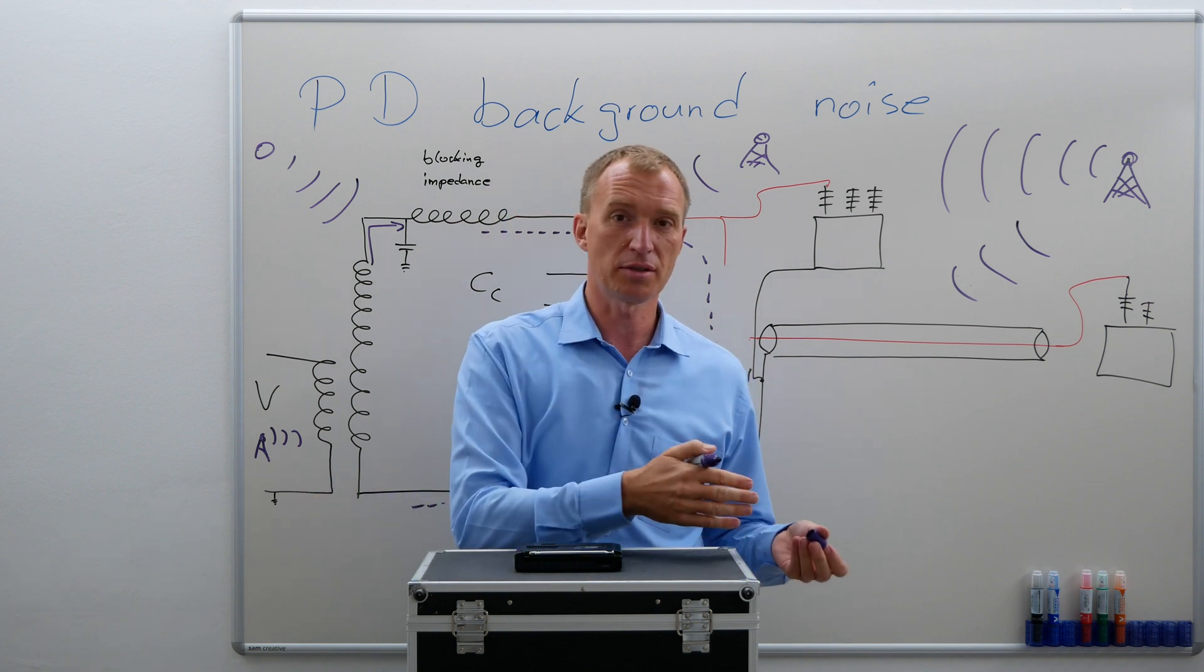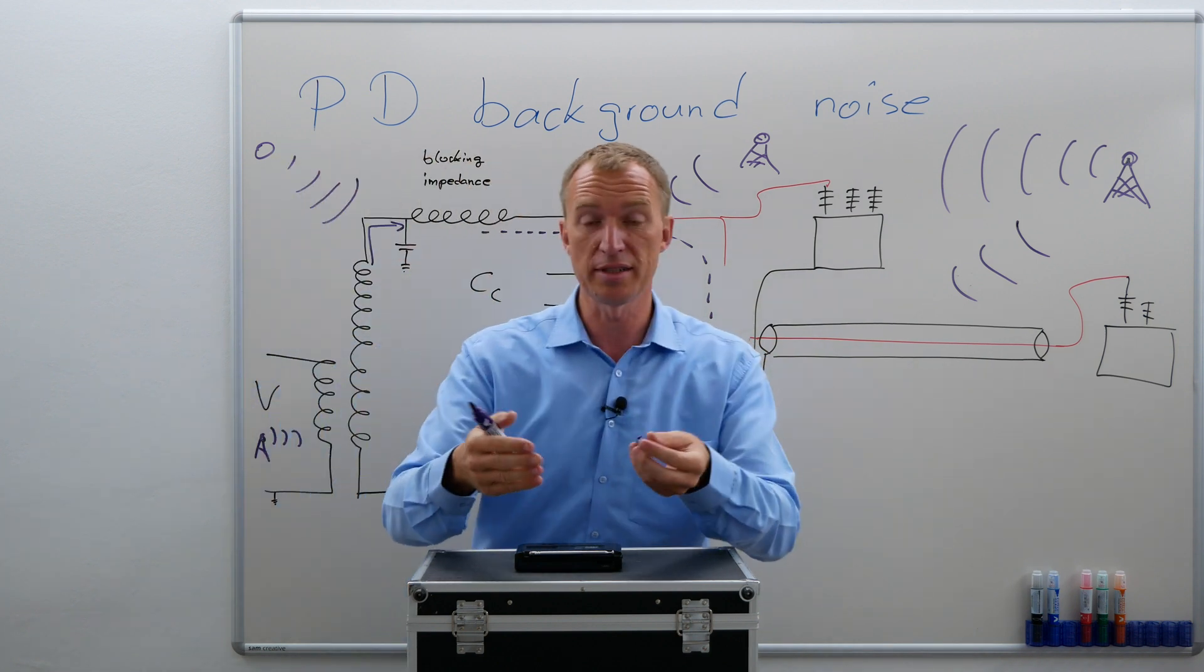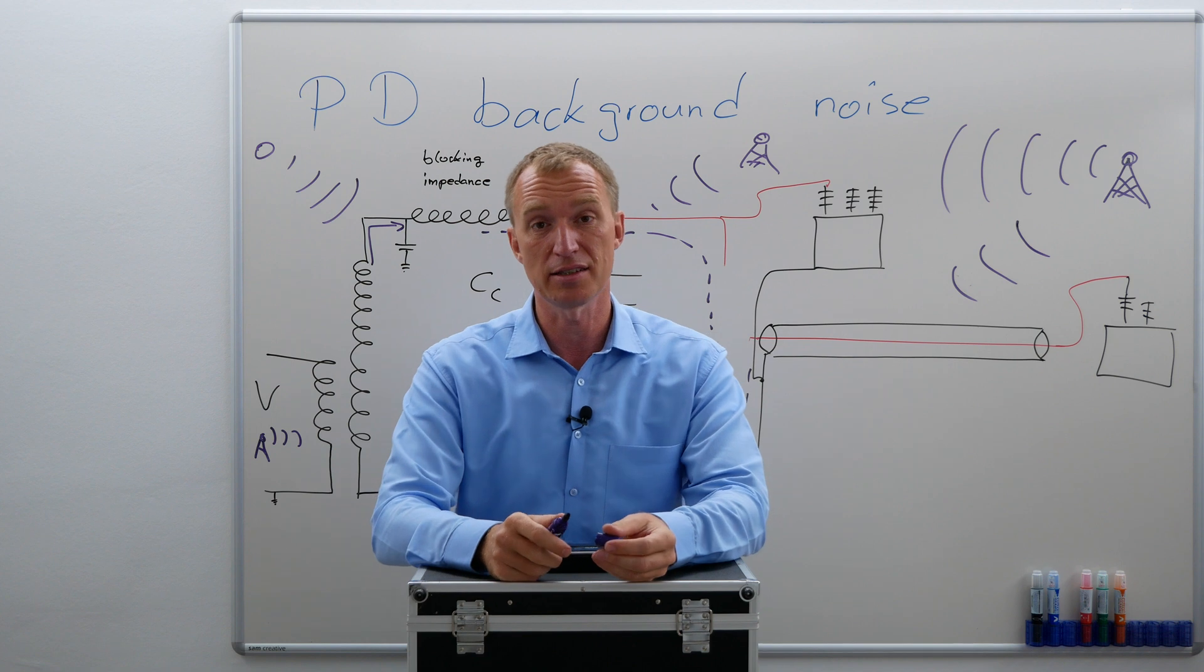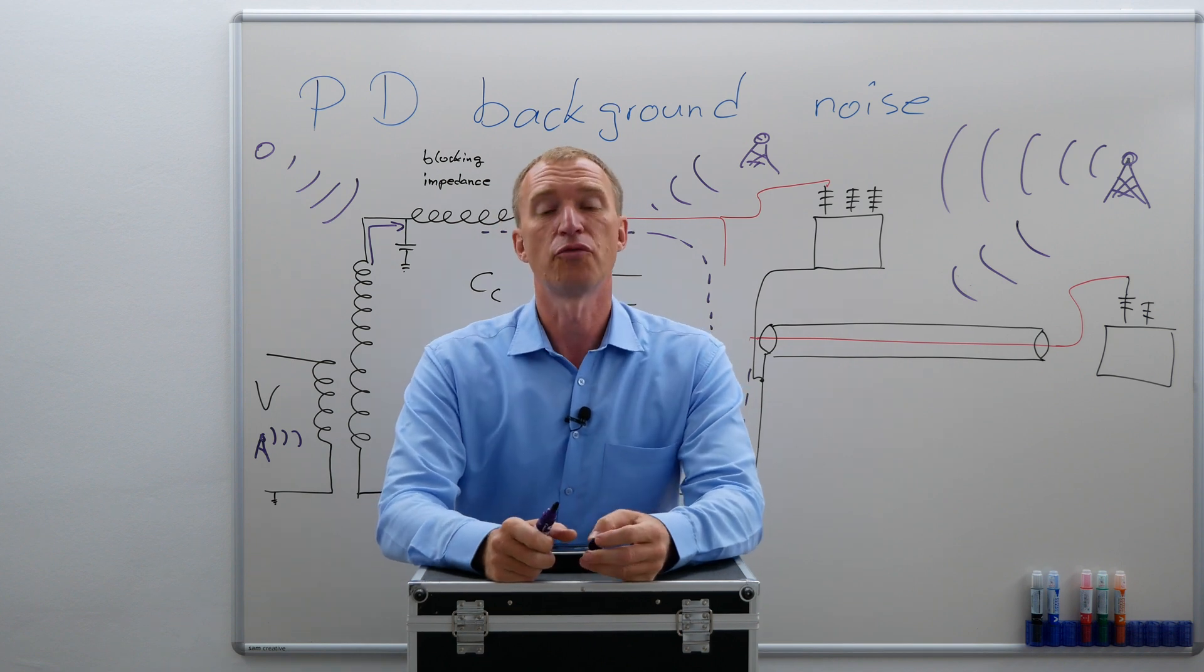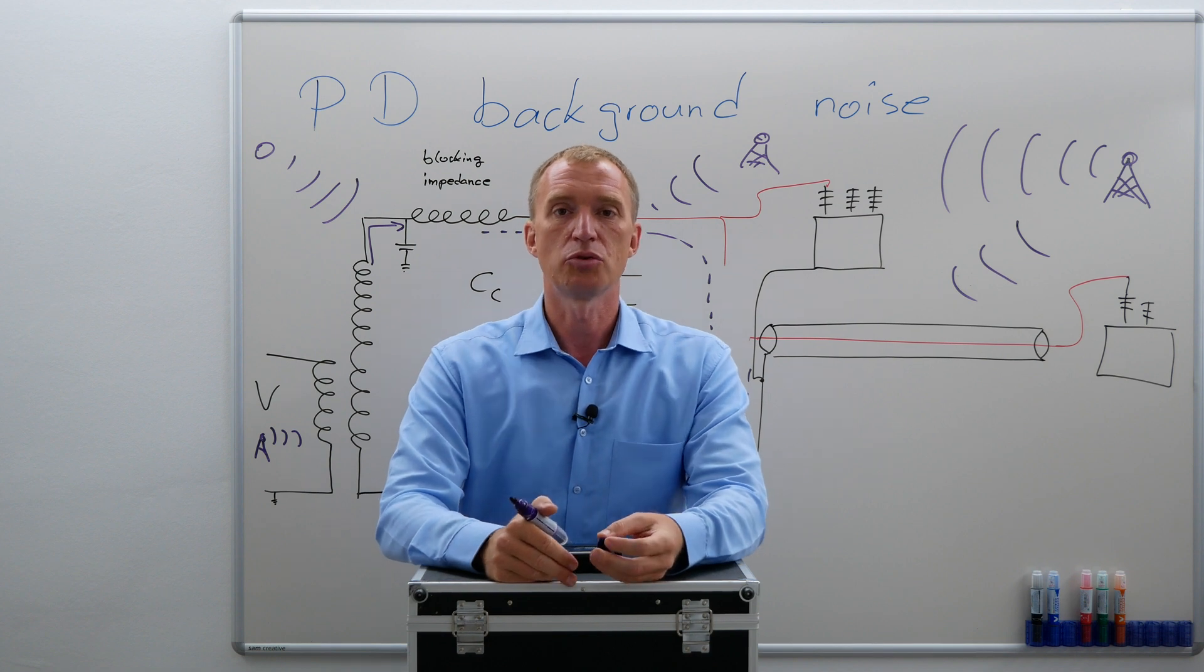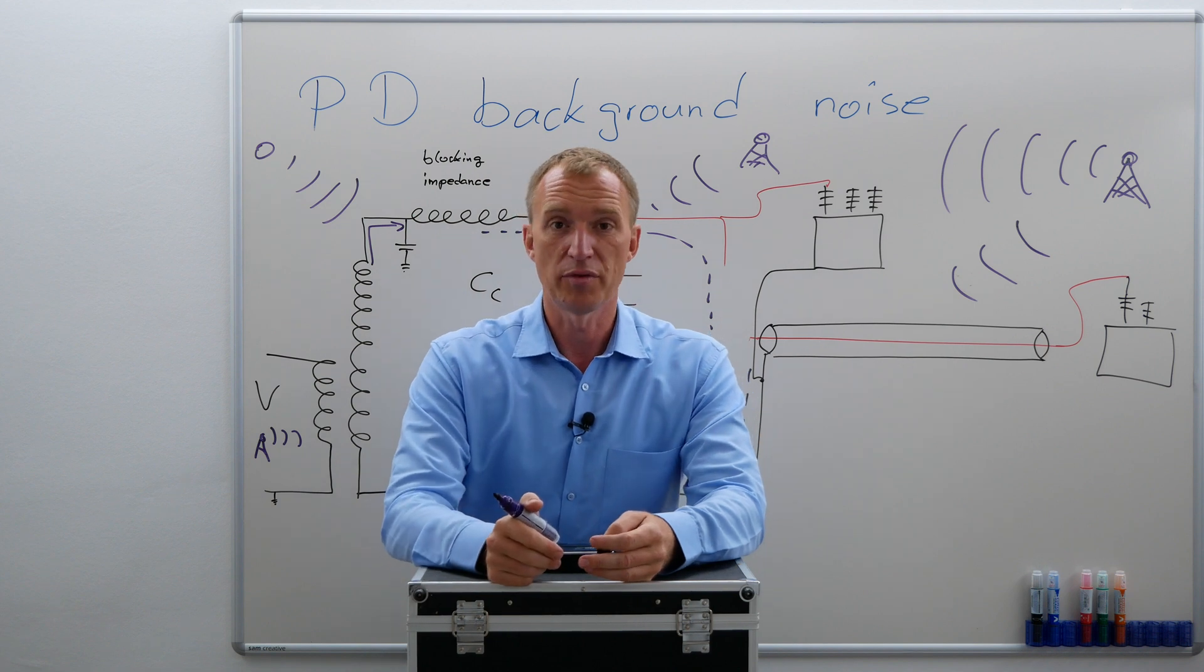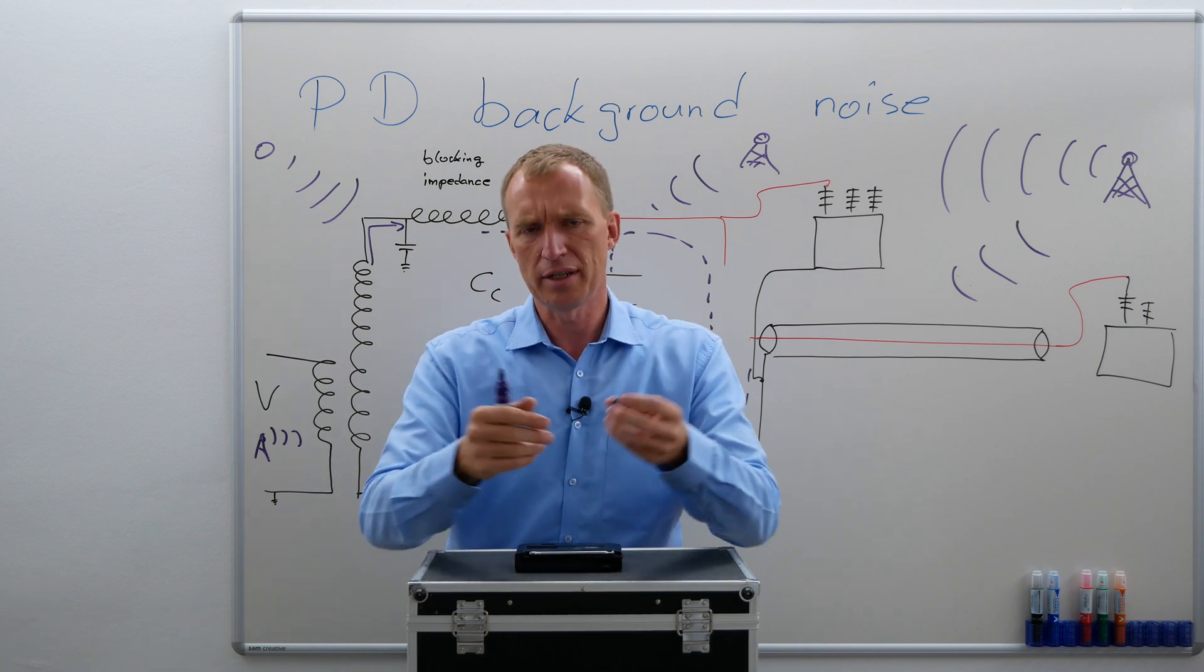There are some manual things you can do. One of the most important ones is the blocking impedance. That is the reason it is actually required by the IEC 60270. And fortunately, most digital devices give you a possibility to reduce the noise in one way or the other. Some of them do it automatically. Some of them you do it manually, digitally.